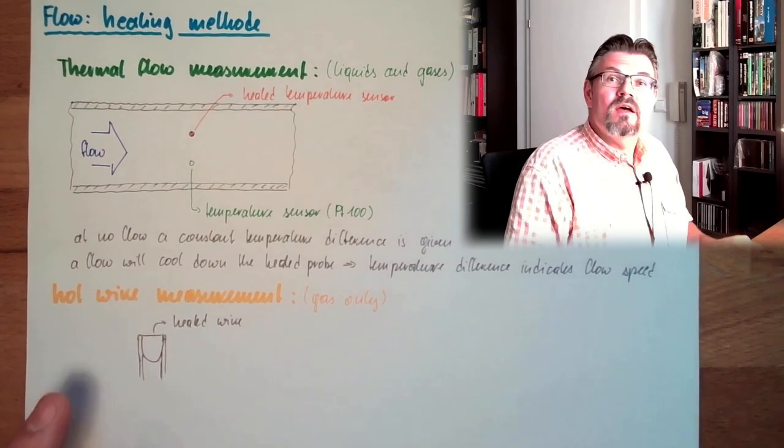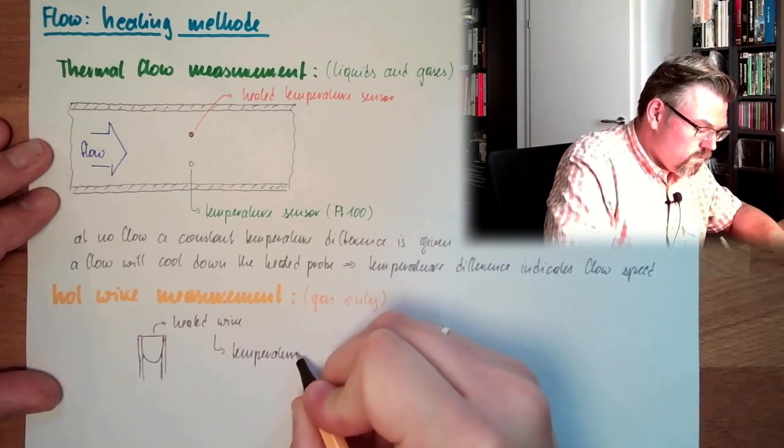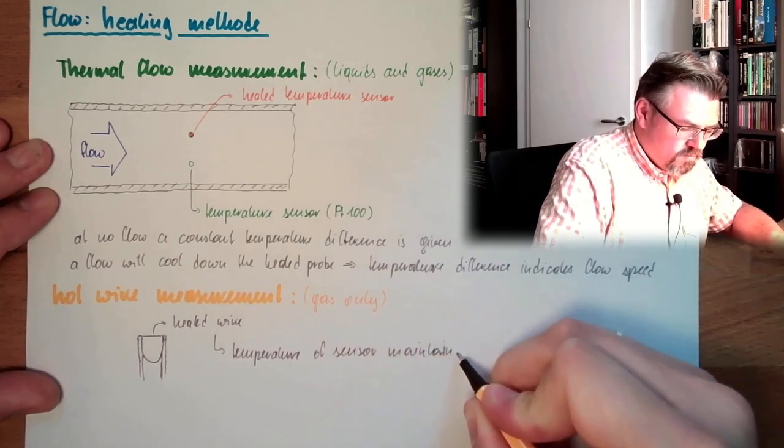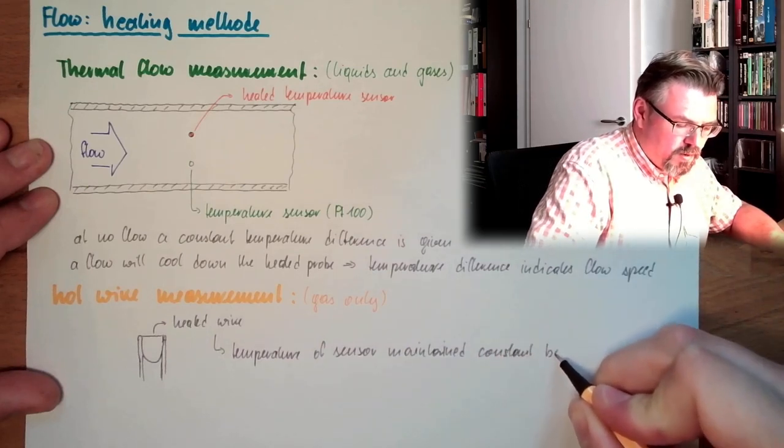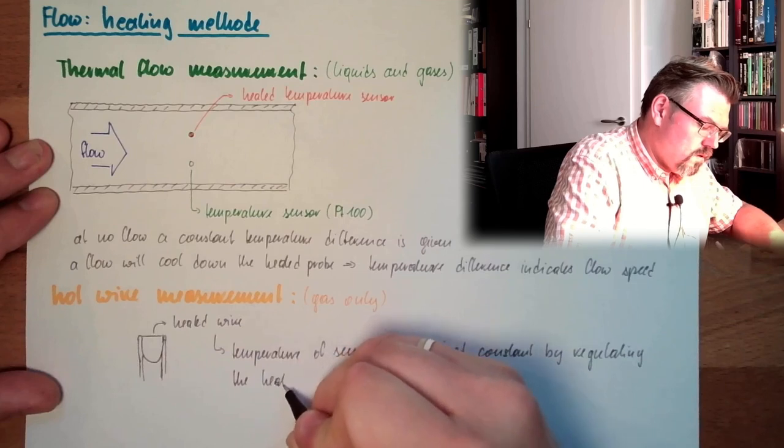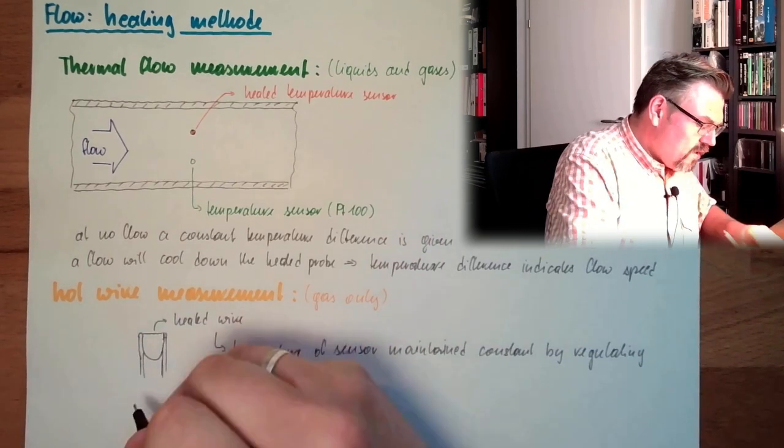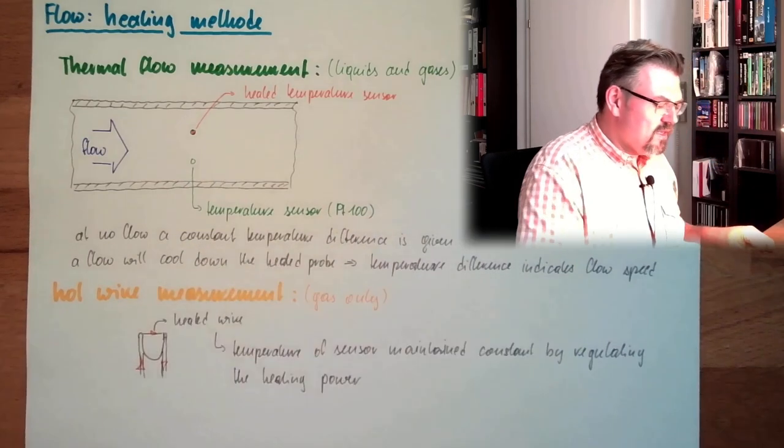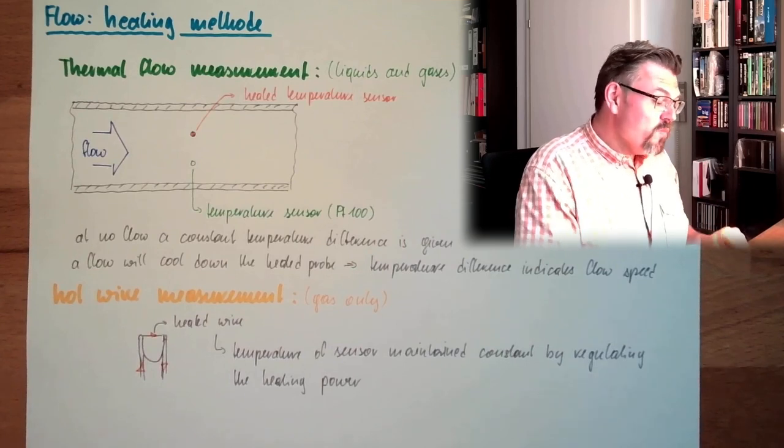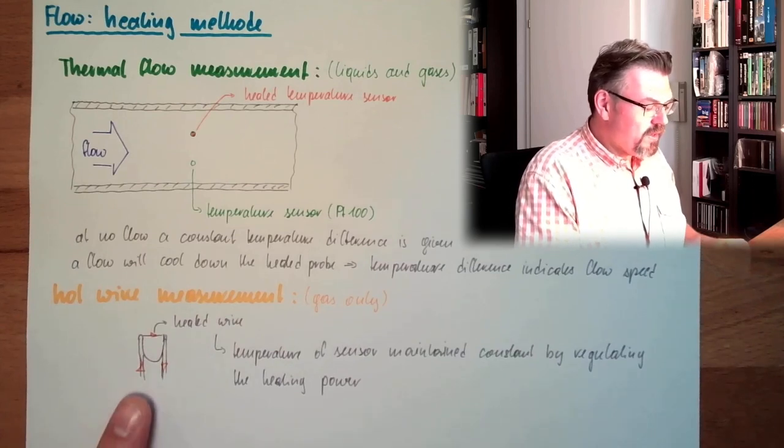And the temperature of the sensor needs to be constant. So the temperature of the sensor is maintained constant by regulating the heating power. So here we are regulating the heating power, there's a current, a heating current driven through this hot wire. And because it's always chilled, wind chill factor and so on, we need more or less heating power to keep the temperature of the wire at the same level. So we maintain the temperature.